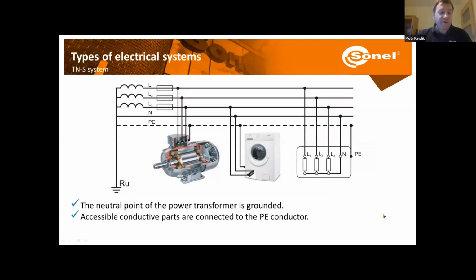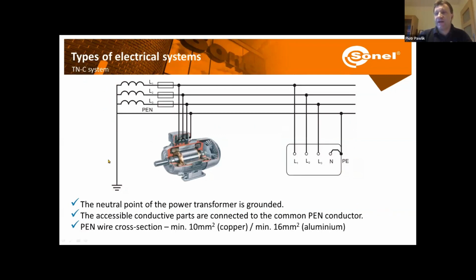Okay, so now let's look at the automatic disconnection of supply. Before I get there, let me quickly discuss different types of electrical grids. So here we have TN systems. In TN systems, the transformer is connected to the ground, and the accessible parts of different devices, their protective channels, are connected through a transformer. Now, in case of a TN-S system, the neutral and protective conductors are separated. In case of a TN-C, again, the transformer is grounded. Accessible parts and covers of different devices are connected through the transformer, but the protective and neutral channels are combined into one, so that's the PEN channel.